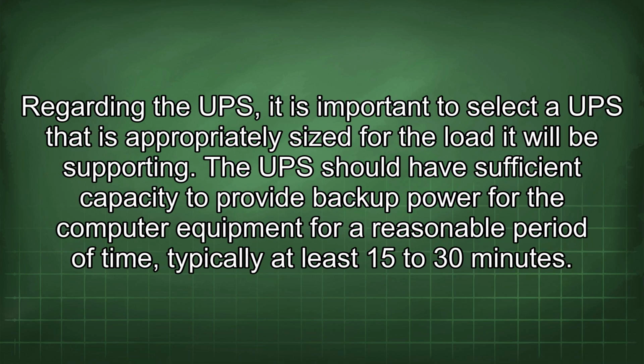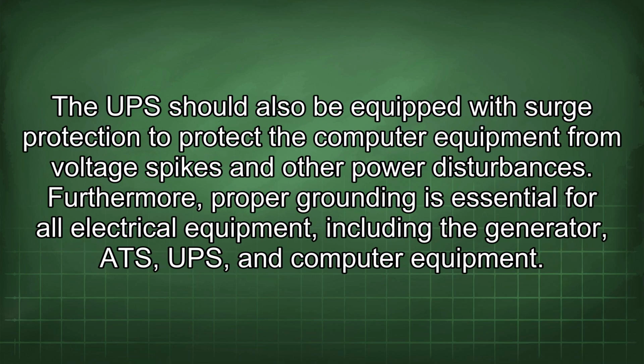Regarding the UPS, it is important to select a UPS that is appropriately sized for the load it will be supporting. The UPS should have sufficient capacity to provide backup power for the computer equipment for a reasonable period of time, typically at least 15 to 30 minutes. The UPS should also be equipped with surge protection to protect the computer equipment from voltage spikes and other power disturbances. Furthermore, proper grounding is essential for all electrical equipment, including the generator, ATS, UPS, and computer equipment.